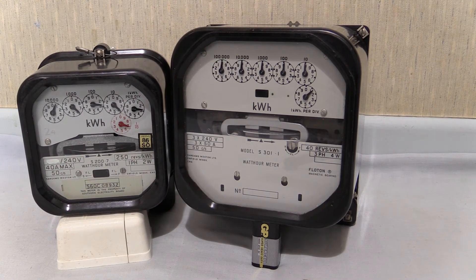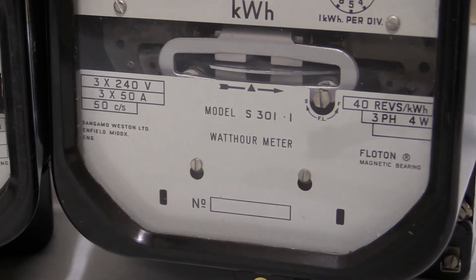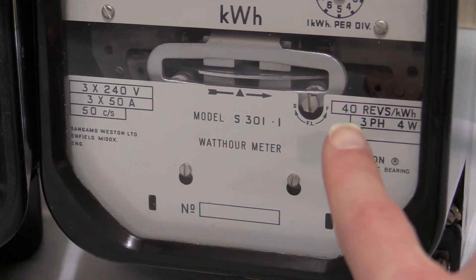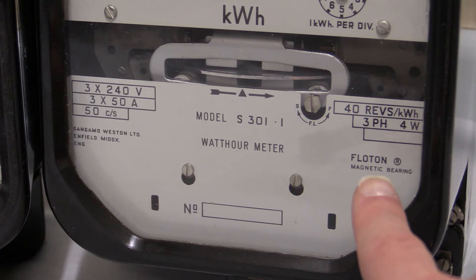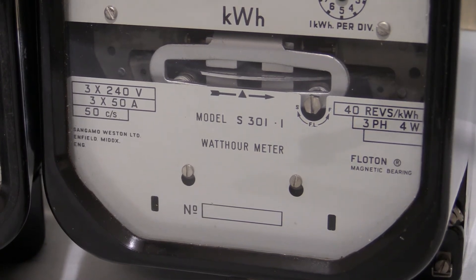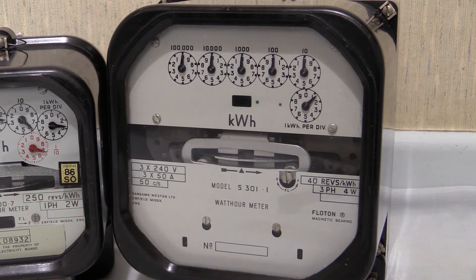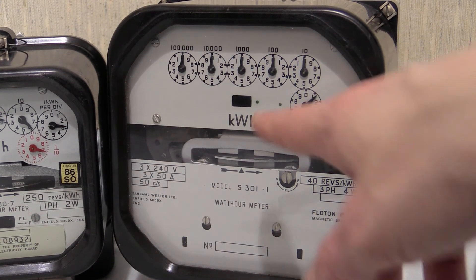Let's continue zooming in and have a quick refresher of the characteristics. The S301.1 is three times 240 volts, 50 hertz alternating frequency, three times 50 amps — that's per phase, of course. It has a very slow 40 revs per kilowatt hour, three-phase four-wire. Both instruments have a Floton magnetic bearing. There's no serial numbering on the S301.1, so I don't know its age. When I bought it, it didn't have any reading on it but it did come with a couple of un-crimped anti-tamper seals. I think it may have been calibrated and put on a shelf waiting to go into service, and then electronic meters came along and it came up for sale. I don't really think this one's ever been used.